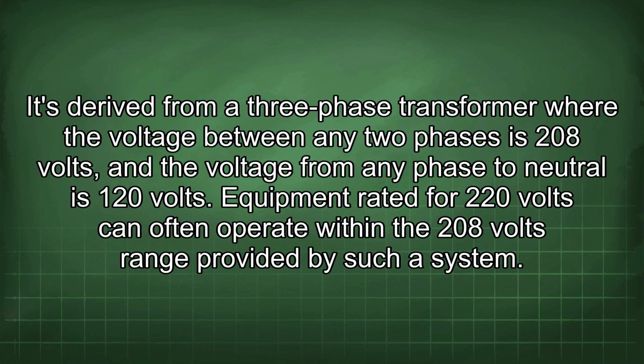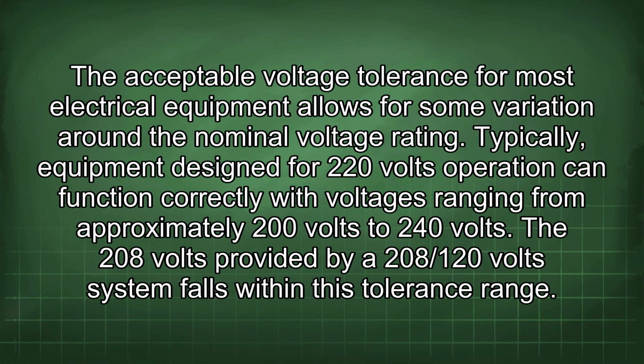It's derived from a three-phase transformer where the voltage between any two phases is 208 volts, and the voltage from any phase to neutral is 120 volts. Equipment rated for 220 volts can often operate within the 208 volts range provided by such a system. The acceptable voltage tolerance for most electrical equipment allows for some variation around the nominal voltage rating. Typically, equipment designed for 220 volts operation can function correctly with voltages ranging from approximately 200 volts to 240 volts.